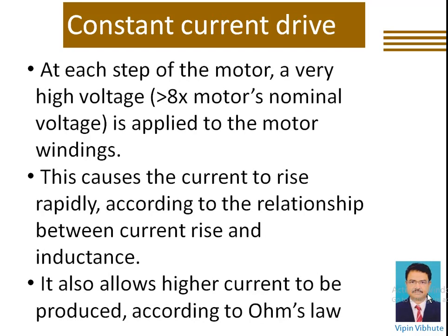Now how is it achieved? At every step the motor is given a high voltage, approximately 8 times the nominal voltage, to the windings. By applying high voltage, the current rises rapidly according to the inductance of the coil, and a rapidly rising current is produced according to Ohm's law. This high rising current will start the motor with the required torque and speed.